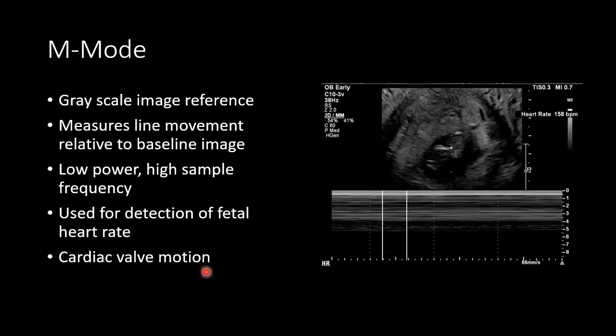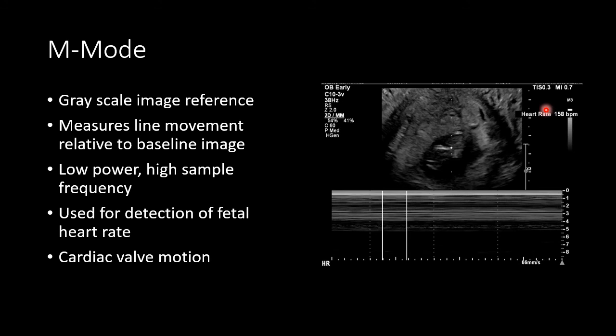M-Mode imaging is not a true form of Doppler imaging, but it is a useful low power form of imaging to detect and quantify motion. A grayscale reference image is obtained, a point of reference is then set, and the motion with respect to that initial reference image is recorded over time. That motion can then be quantified — in first trimester ultrasound it can be used to determine the fetal heart rate, and in echocardiography it can be used to calculate the excursion of the valve leaflets. It is a low power form of imaging, and therefore it is safe to use in the first trimester because of its low thermal index and low mechanical index. We try to avoid any forms of spectral wave or color Doppler in the first trimester fetus.